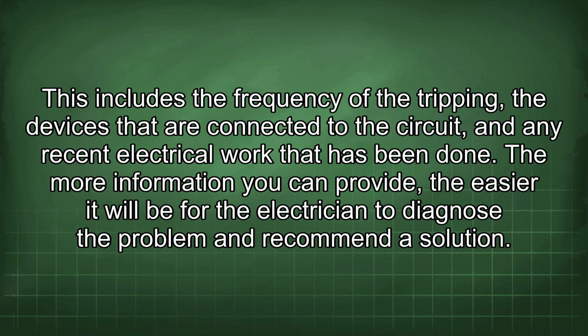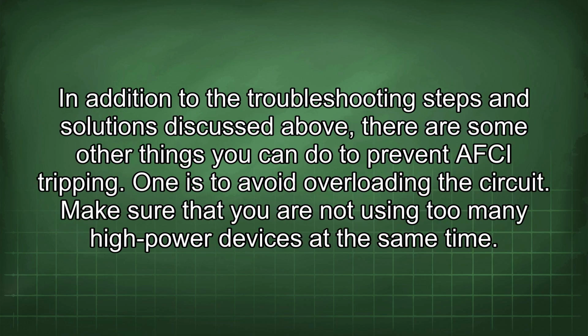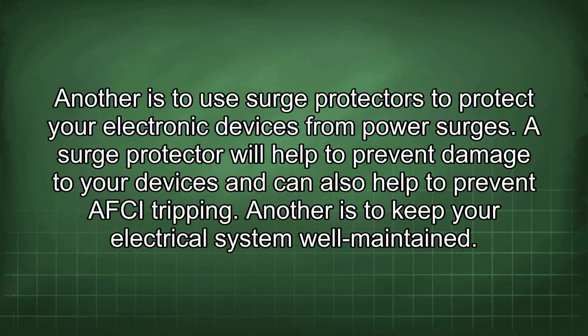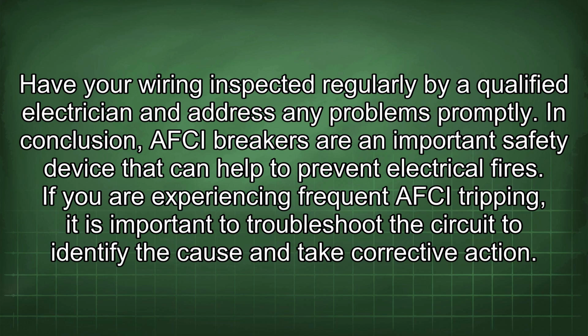In addition to the troubleshooting steps and solutions discussed above, there are some other things you can do to prevent AFCI tripping. One is to avoid overloading the circuit. Make sure that you are not using too many high-power devices at the same time. Another is to use surge protectors to protect your electronic devices from power surges. A surge protector will help to prevent damage to your devices and can also help to prevent AFCI tripping. Another is to keep your electrical system well maintained. Have your wiring inspected regularly by a qualified electrician and address any problems promptly.